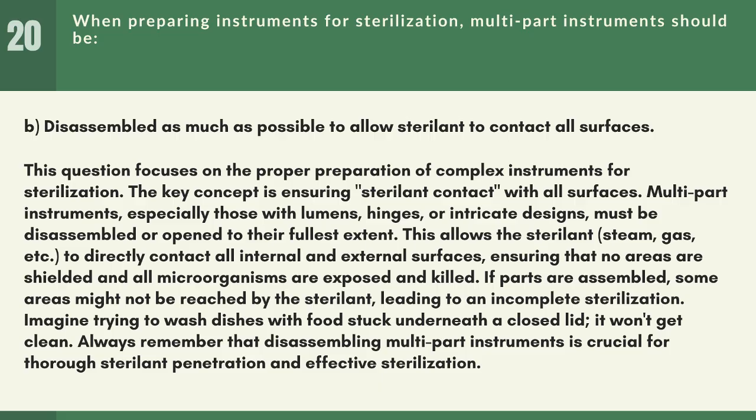This question focuses on the proper preparation of complex instruments for sterilization. The key concept is ensuring sterilant contact with all surfaces. Multi-part instruments, especially those with lumens, hinges, or intricate designs, must be disassembled or opened to their fullest extent. This allows the sterilant, steam, gas, etc., to directly contact all internal and external surfaces, ensuring that no areas are shielded and all microorganisms are exposed and killed.